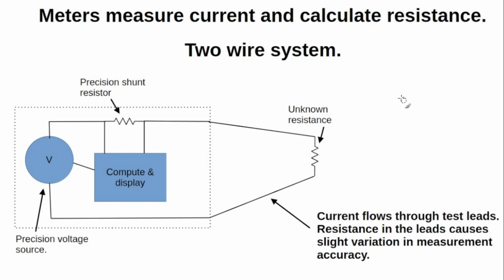The way it works inside the meter generally—this is just an approximation, a simplification—the meter has a voltage source, and it knows the value of that voltage, and it's feeding through a shunt resistor that has a very precise value, and then the current goes out through your test resistor and comes back. So the meter measures the current by measuring the voltage drop across its known resistance, and it knows the voltage that it's feeding, and then uses those values to calculate this unknown resistance.